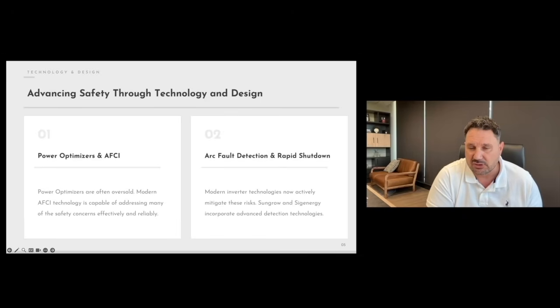They are often oversold. Modern day AFCI technology is capable of addressing many of the same safety concerns which optimizers did address. One of the challenges with optimizers is that they introduce an additional component, and that inherently introduces additional connection points into the system, which in turn increases the number of potential points of failure. DC arc faults are widely recognized as a leading cause of PV fire.